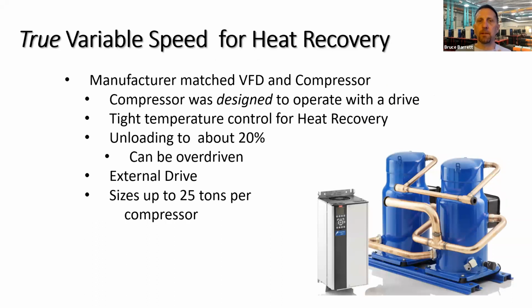Talk a couple slides. I mentioned capacity, the ability to slow down. Each compressor can unload to about 20% in a water-cooled environment. They do have an external drive. Since we have to mount that drive on the equipment somewhere, we have to be conscious of the footprint of the machine. If you've got to get it through a 36-inch door, we've got some variations to be able to do that.